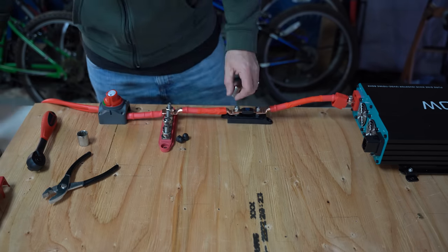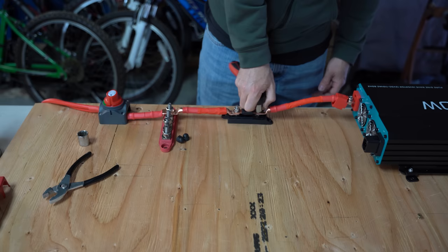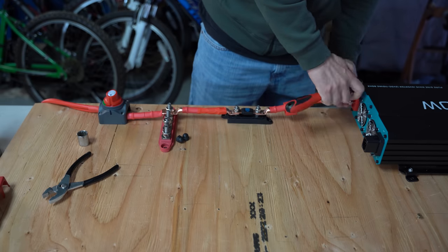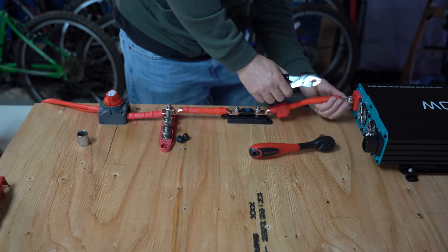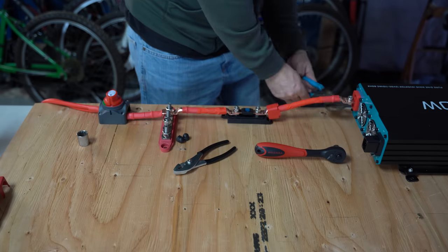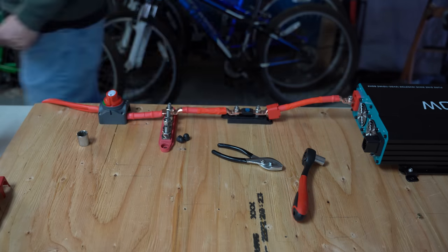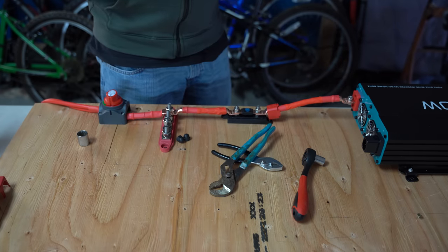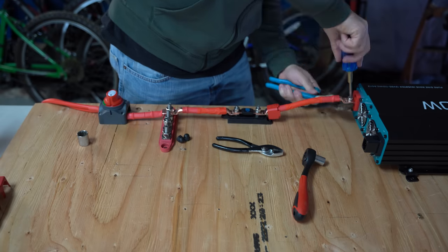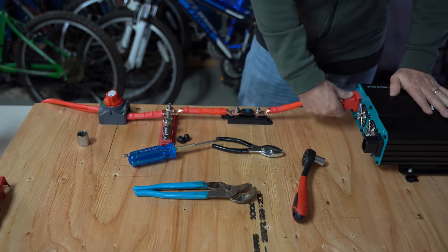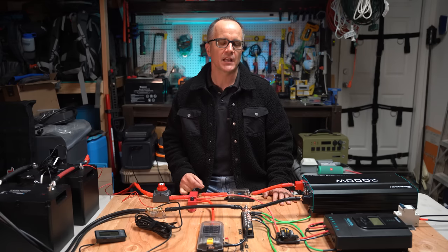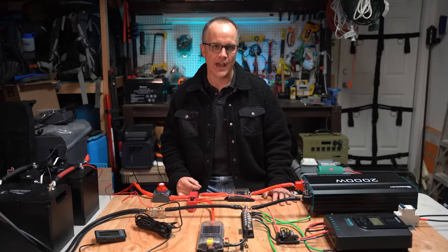I waited until I finished connecting everything as these cables are so thick that you really can't bend them. I had mounted a few of the components earlier before cutting off the cables, and I found that if the connections on the end of the cables are even something as short as a quarter of an inch off, I have to then move the bus bar or fuse holder to get everything to connect properly. So let's run through the negative connection from the inverter to the battery.